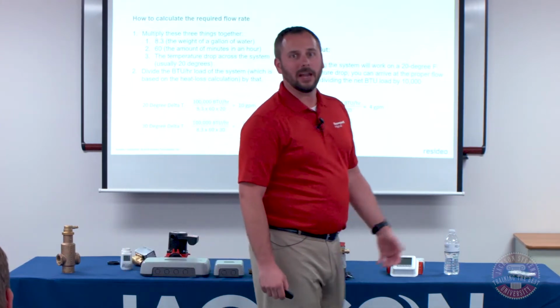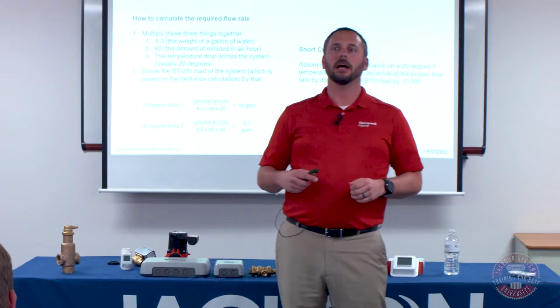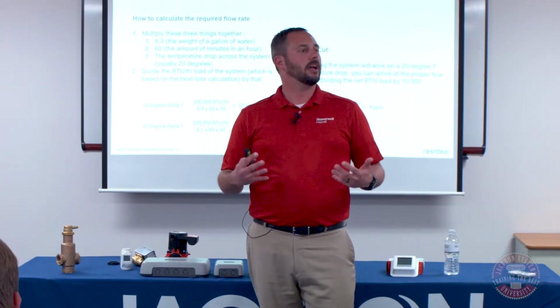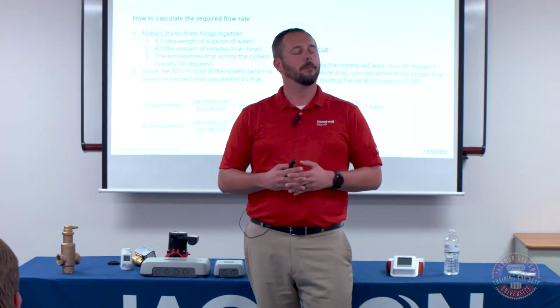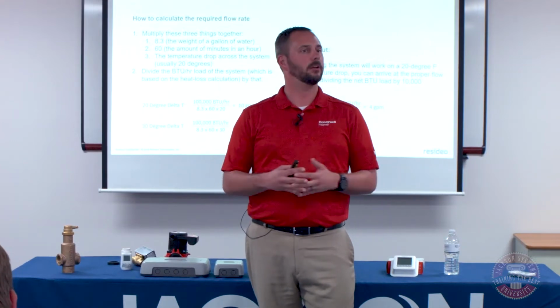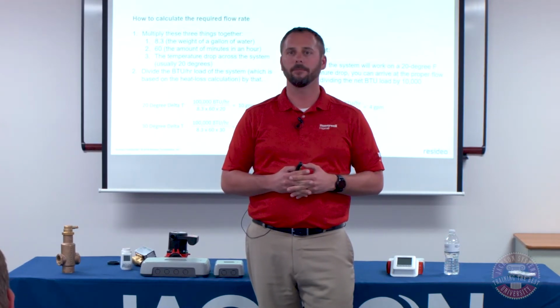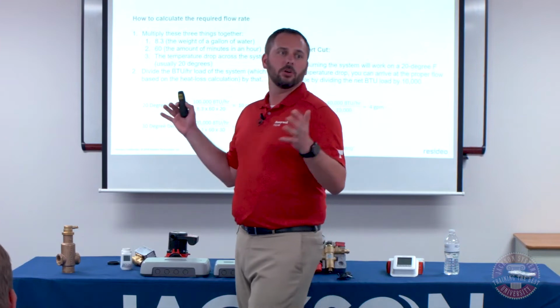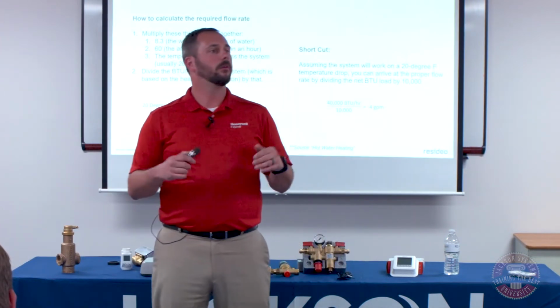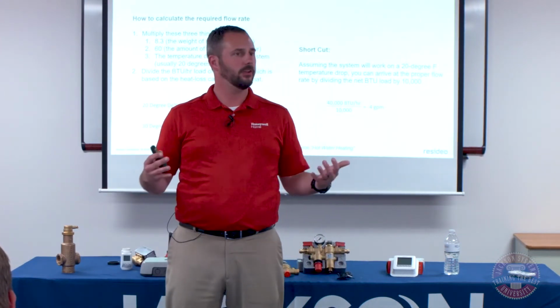Now, there's some other things you've got to keep in mind with that. You've got to make sure that you're not eroding, your pipe sizing is correct, and there's other things going on. But as far as pump sizing, you've now got an idea real quick off the flow rate. So that's if you're doing one pump for everything, or one pump for the boiler. So what if we're doing a pump for the system?